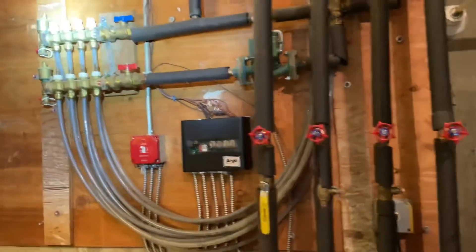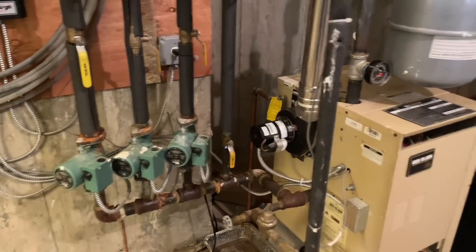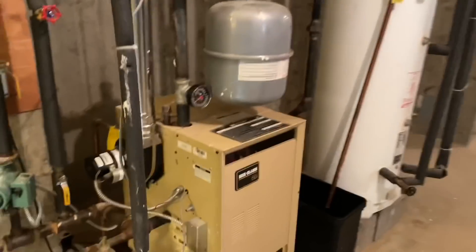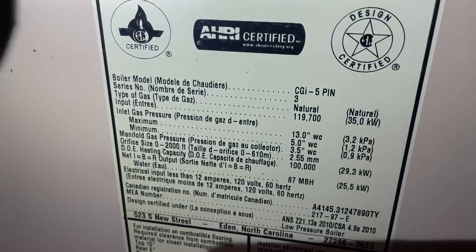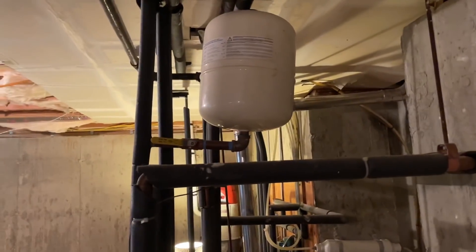Mike asks the homeowner to raise the heat on the zone that comes out of vents. He identifies the boiler as a Weil-McLain CGi-5, power-vented with an inducer motor and stainless steel B-vent. There's also an indirect-fired water heater and an expansion tank up above, which is visibly weighing down — a sign it's waterlogged.